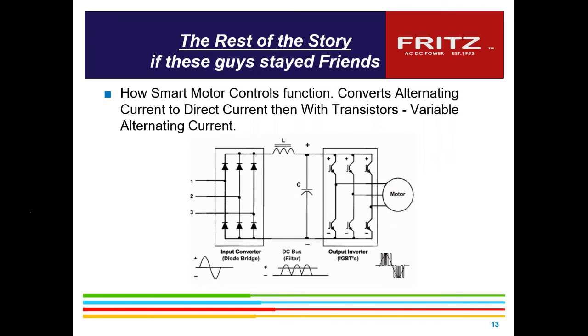And I do give a class on all the various types of ways of starting, running and controlling motors, with VFDs, soft starts, old part winding starts. There are also ways of doing phase conversion, with devices where you can utilize two input phases, take single phase input, still build the DC, and then build true three-phase output and run the motor. So we use a lot of these for phase conversion also.